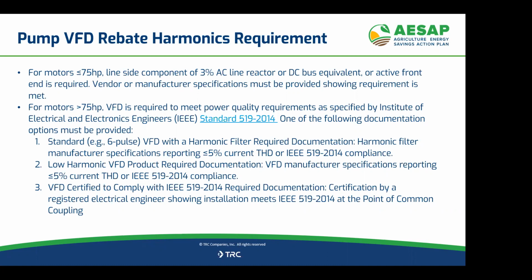Really good info, it's really important that we do this. Over the years working with PG&E's pump efficiency program, we've watched so much more load and power factors dropping off significantly. I remember when I was in the field pump testing in the 80s and 90s, you rarely saw any power factor below 90%. Now it's almost all below 90%. All that heat buildup on the lines, and people running VFDs much less efficiently, much lower hertz than they should be, running them down to where the pumps are really running in inefficiency. The result is heat and resistance in every aspect of your system.